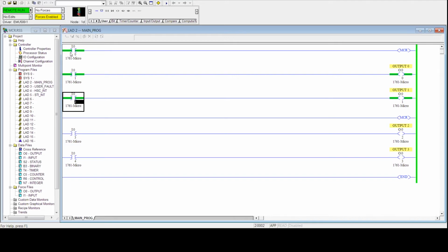But if we turn this off, we turn off this MCR. Look. These inputs are true, but it will not let our outputs become true. That's what the MCR essentially does. The MCR controls a block of code from letting their outputs turn on. But it only controls a block. If you imagine this right here, and this line right here being a block, that's all that this controls.